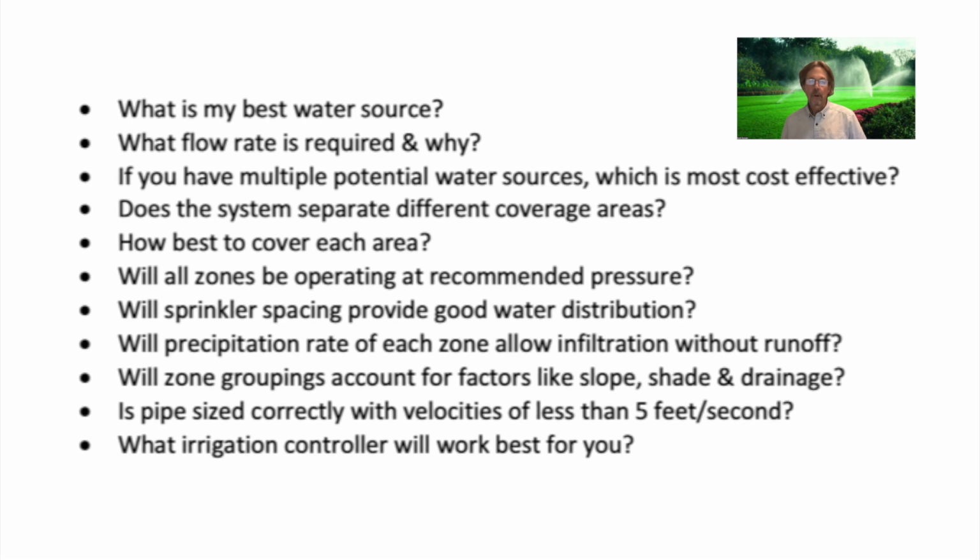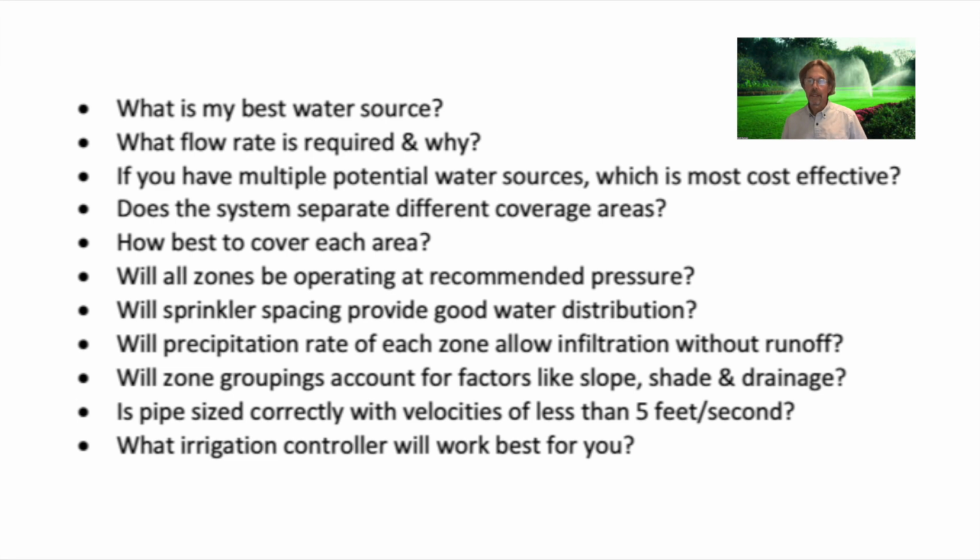Is pipe sized correctly with velocities of less than 5 feet per second, which is an industry standard? Pipe must be sized to maintain flow speeds at less than this industry standard. If not, sooner or later, leaks will occur.